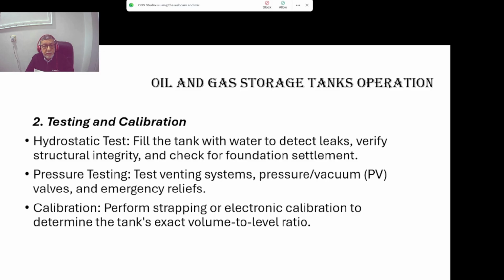Testing and calibration also. Hydrostatic test: fill the tanks with water to detect leaks, verify structural integrity, and check for foundation settlement. This is very important, the foundation settlement, because we have to check the foundation with the loading of tanks, yani tank full with water. Pressure testing also: test venting system, pressure vacuum valve, and emergency relief valves. Calibration: perform strapping or electronic calibration to determine the tank's exact volume to level ratio.